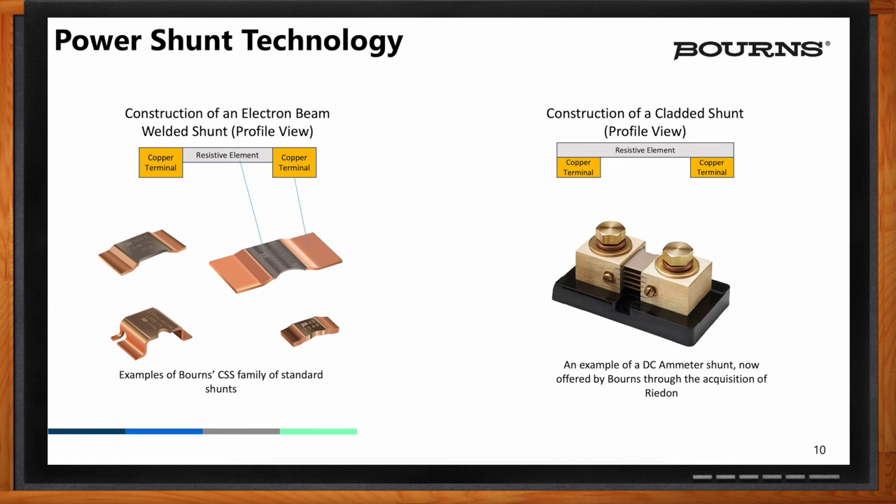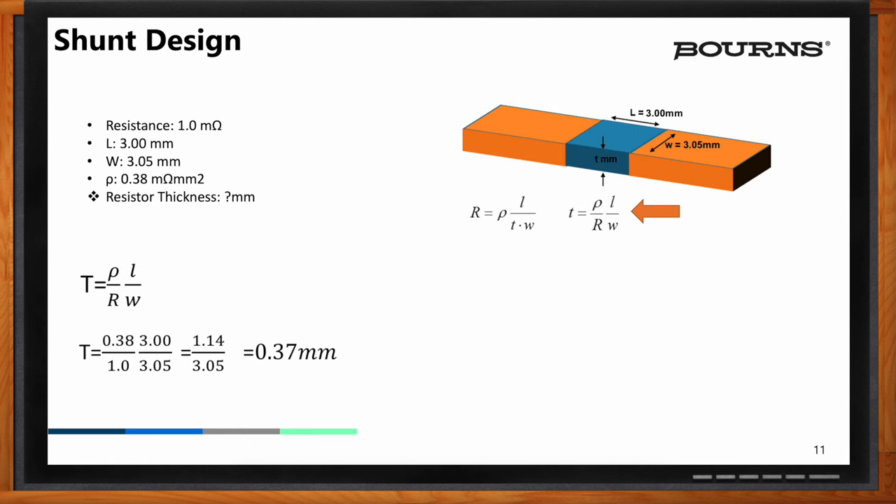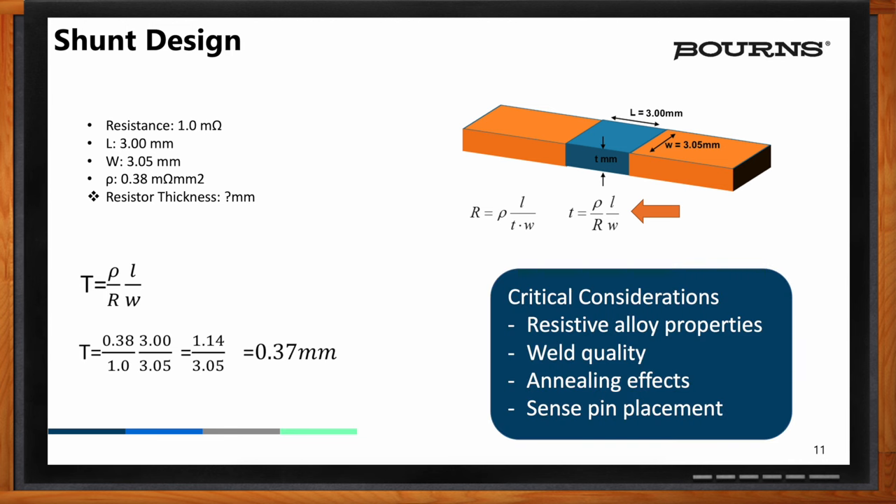Moving on — and I'm going to nerd out a little bit here. The shunt resistor values are a function of material volume, material type, and size. Given the material constant of 0.38 milliohms per square millimeter, to achieve a one-milliohm resistance, you'll need a material thickness of 0.37 millimeters with x and y dimensions of 3mm by 3.05mm. It is more of a volumetric calculation, but the material alloy is important, and how you form and weld it also affects the shunt precision.